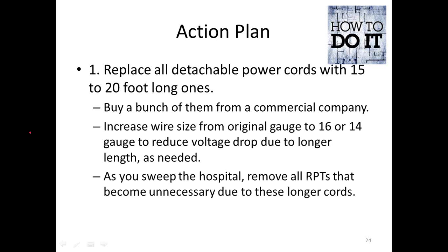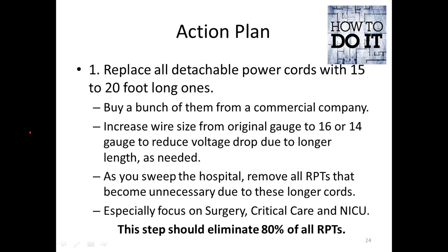Then you sweep through the hospital. You have your technicians go through every department one by one and remove every single short power cord and plug in a long power cord. You do this to virtually every piece of equipment in the hospital, except equipment that you know is permanently situated beside an outlet and will never need a cord that long. But the majority of your equipment, and virtually everything in an operating room, needs to be changed to these longer cords. So when you do this, you will be able to eliminate as many as 80% of your power strips.